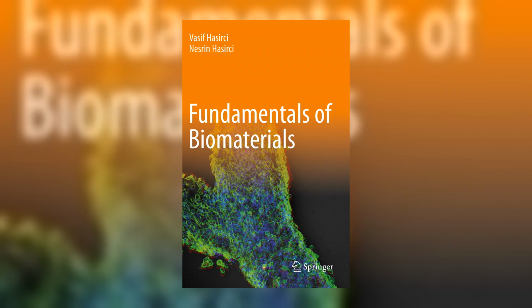This section explains how safety gets judged for a ceramic implant. The safety of a ceramic implant is not read off the intact solid, it is read off what the solid sheds as it dissolves. ISO 10993, Part 14, performs a change of variables.